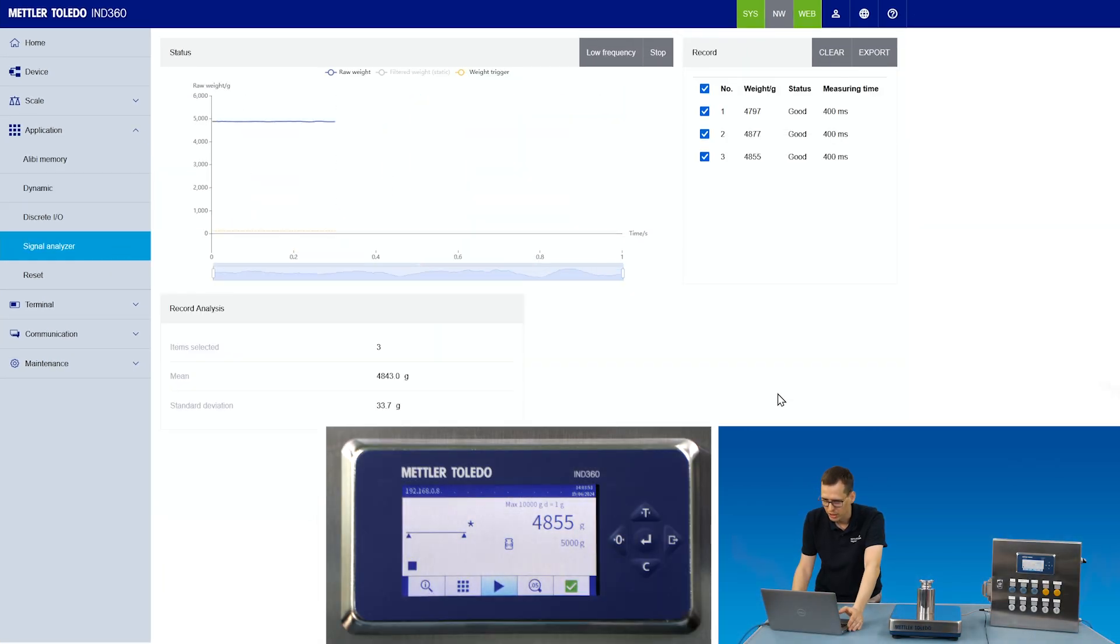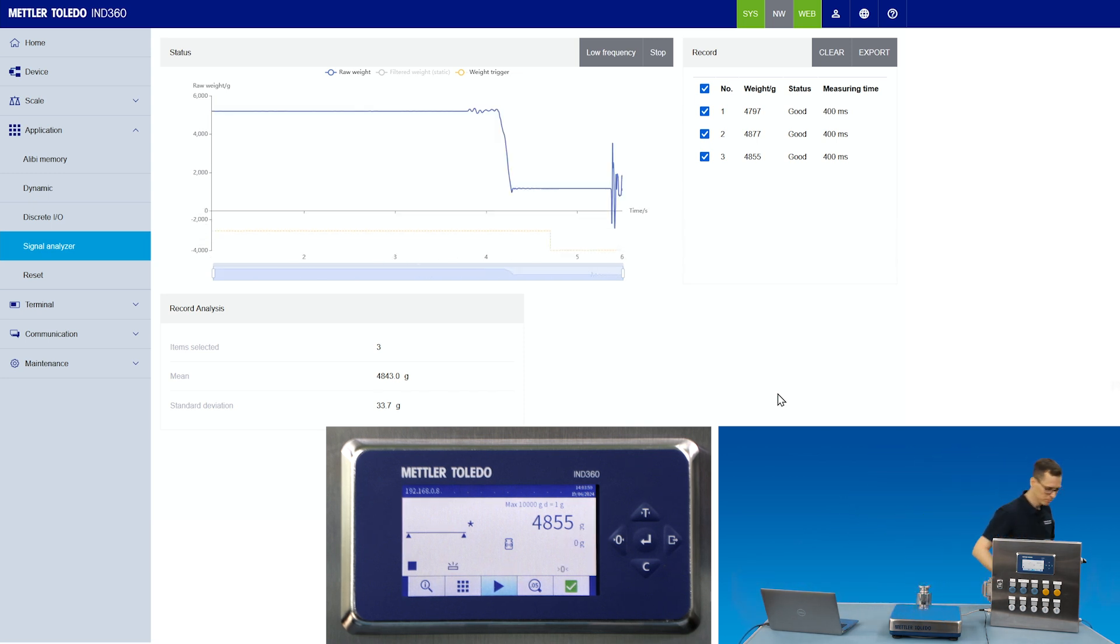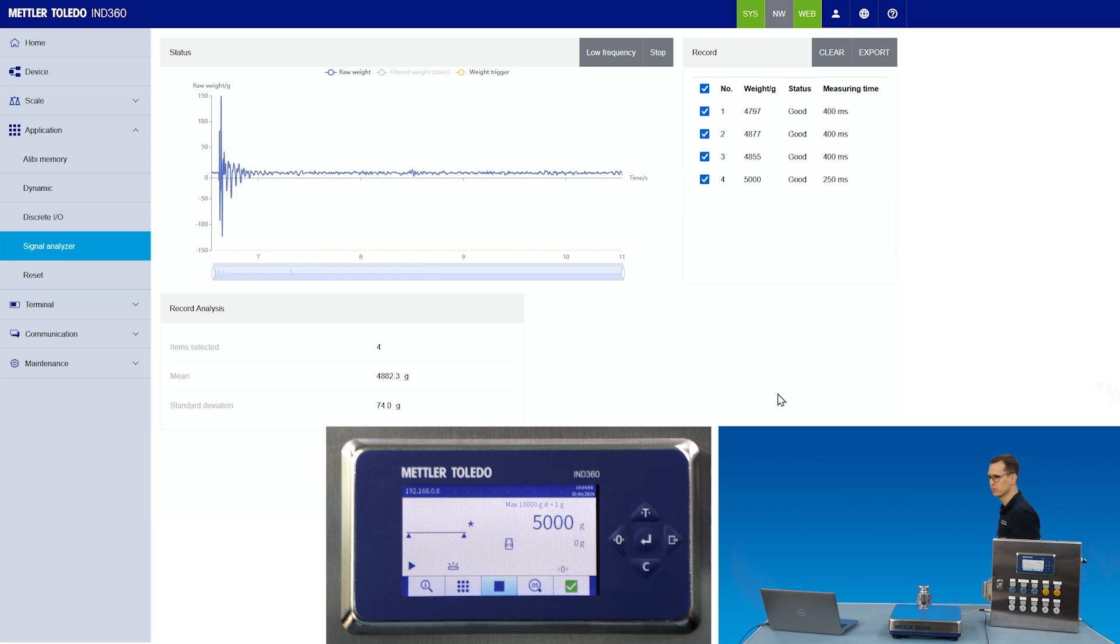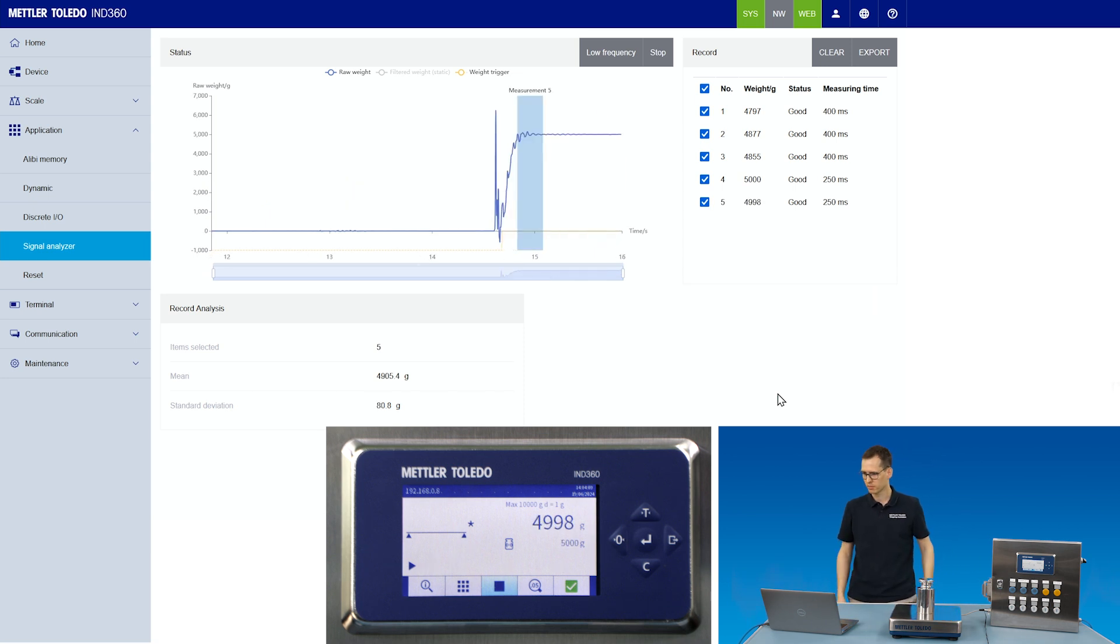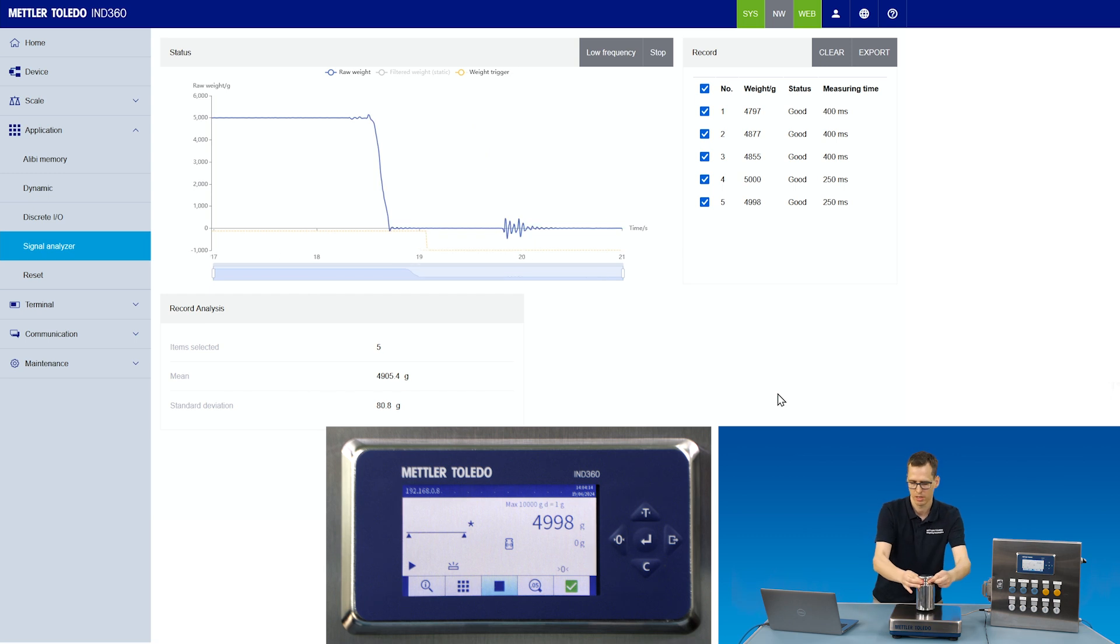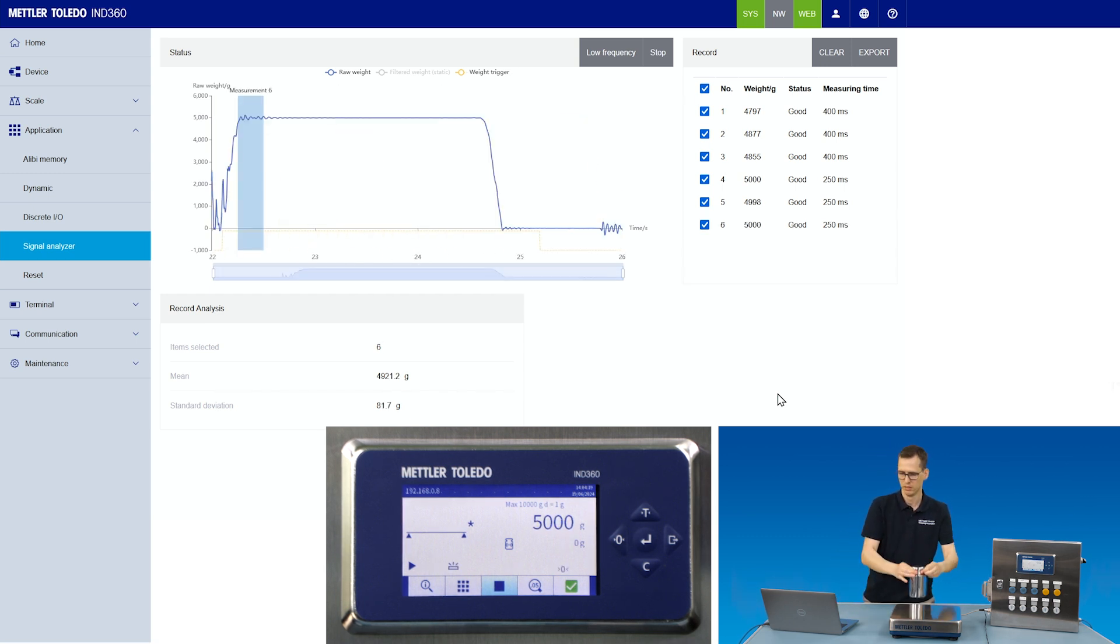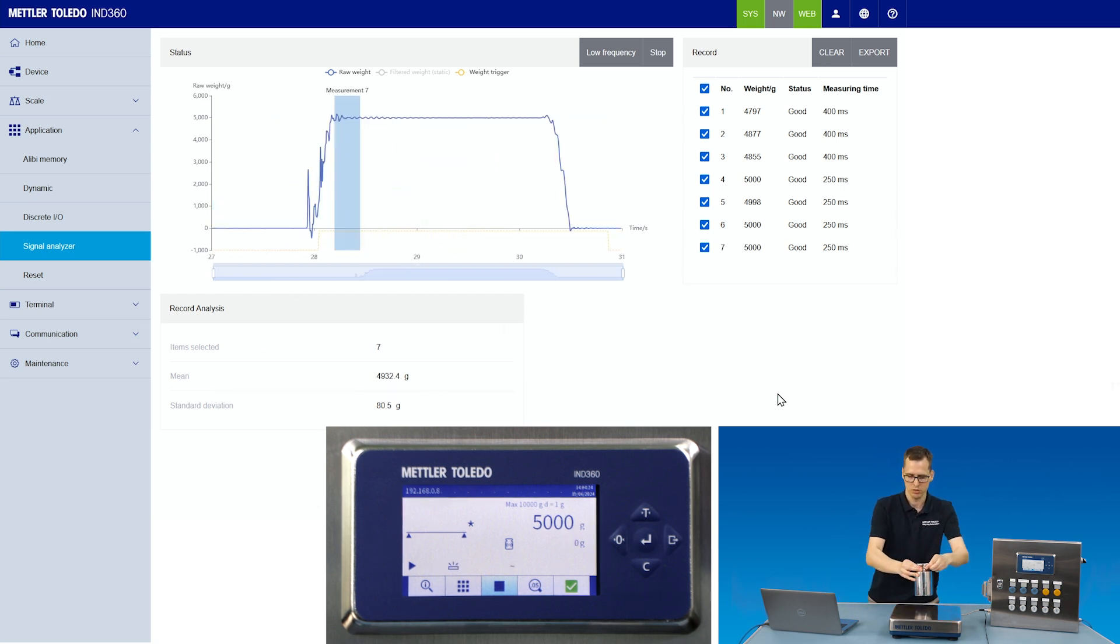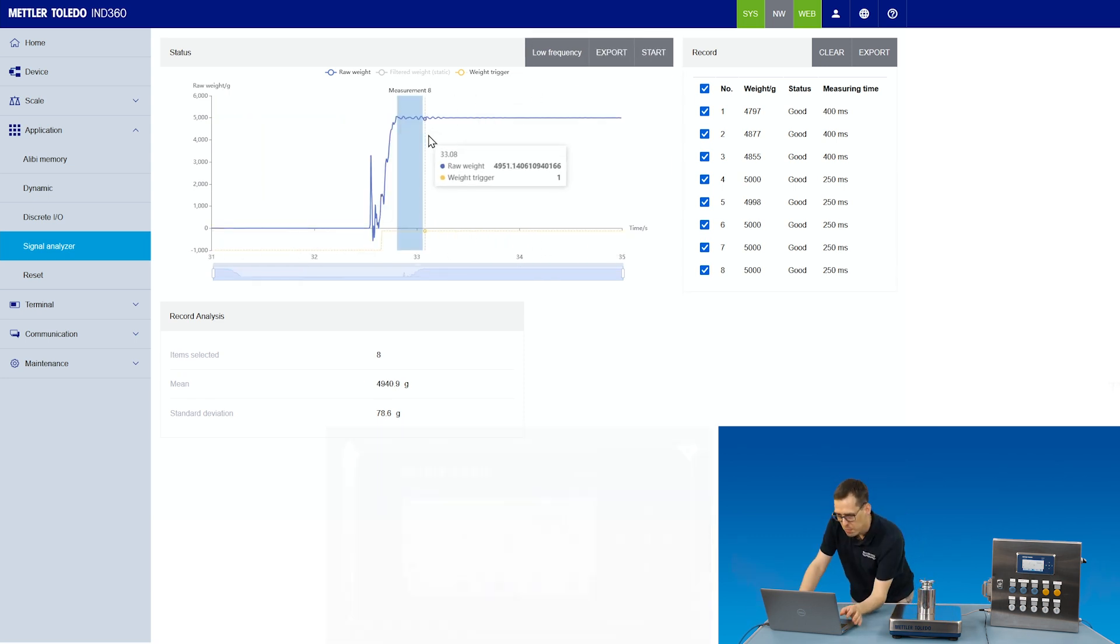Going back to the signal analyzer, starting the data trace and starting the application. And apply the weight again. 4998. 5 kilograms. 5 kilograms. Another try. 5 kilograms. So I stop it again.